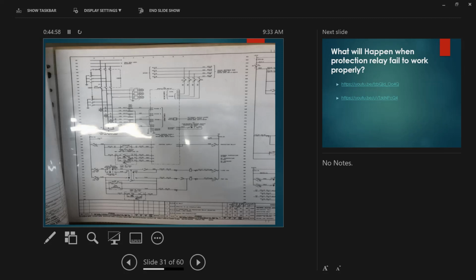Hey, man, I'm already tripped. You're right, it doesn't work as a breaker failure. So if you never disable that and you continue injecting overcurrent, instantaneous, the relay will think there's something wrong with the breaker. I need to activate this. There is some kind of process of logic internally on the relay. Is that an actual internal setting in the relay that can be activated and deactivated? Yeah, you can activate, deactivate.